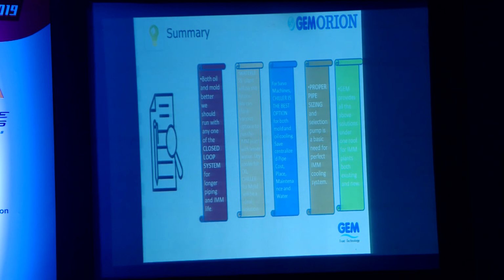We have given so many options. So the summary is, for both oil and mold, we should run with one closed loop system for better piping and mold life. Waterless plant will be the future. We can think of various options to run the plant with lesser water. Dry cooler for oil, chiller, and for mold will be an ideal solution. For servo machines, because we need cooling water for the mold and oil, which is servo, the capacity of the servo heat load is very less. We can save on complicated piping, water distribution, paneling, so one-to-one dedication, so chiller is better.